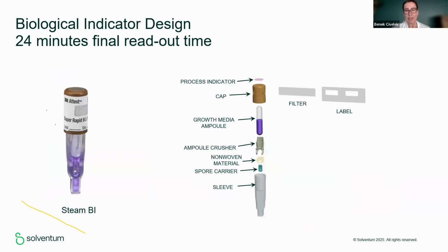Biological indicator design should be different in fast response indicators, because there are several indicators which can result in longer times. It started with 48 hours, it came to 3 hours, and then 1 hour, and now we are talking about minutes. So this technology should reflect the design of the indicator. As you see in the bottom, there is a narrower part of the sleeve, and also there is a non-woven material over it. So this is a perfect place for the microorganisms to grow if the sterilization is not successful. So the design should also reflect the technology.